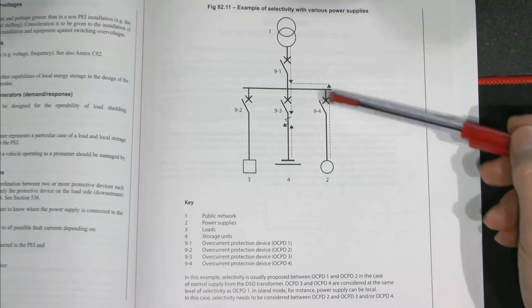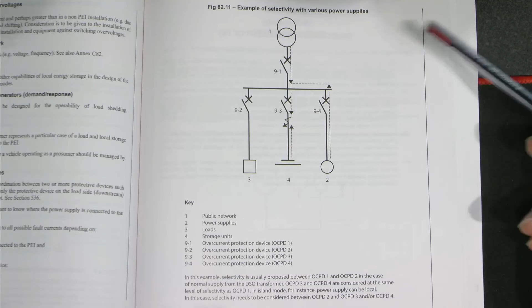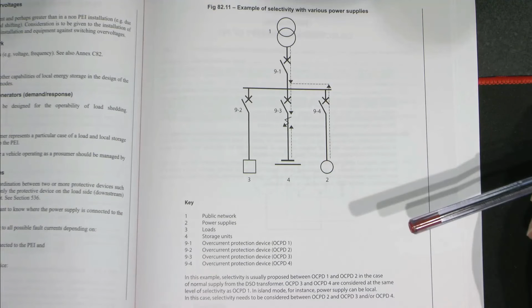And as it says at the bottom here, you also need to consider selectivity. So say you have two devices here and there - if it's coming up from your solar panels going into your batteries, you want selectivity so the most appropriate device actually disconnects. If a fault occurs on one piece of equipment, you don't want something else to be disconnected instead. Say a fault occurred on the cabling between your solar panels, you don't want the batteries to be disconnected, because that's still going to leave the fault open with energy coming from the solar panels.